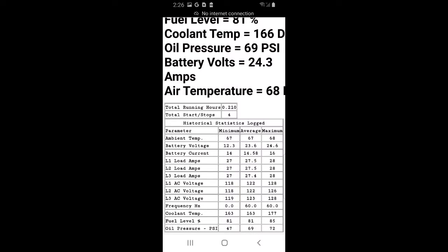Further down on the web page is the display of the historical statistics. Anytime the generator is running, the system will sample all generator parameters and update the statistics. Statistics tracked are total running time, the number of times the generator has been started and stopped, as well as all of the analog parameters the system monitors. Every 10 seconds the table is updated with the minimum, average, and maximum for each tracked parameter. These can be useful for tracking the generator's performance, as well as aiding with maintenance. The tracked data can be reset if and when desired.